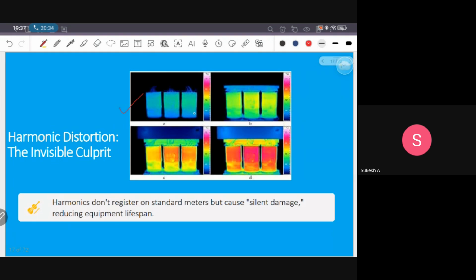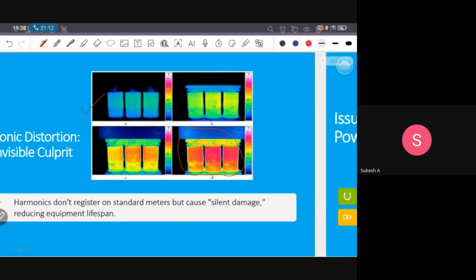Our load is non-electronic. Our load was a resistive load. We have connected a resistive load, and our transformer core is like this. When we increase the harmonics with a power electronic load, we get the coil like this. Our coils are getting overheated, and this transformer is not designed for such a purpose. Such sudden voltage, sudden heating and overloading was not experienced so far, but due to EV integration this is experienced and it may get damaged.